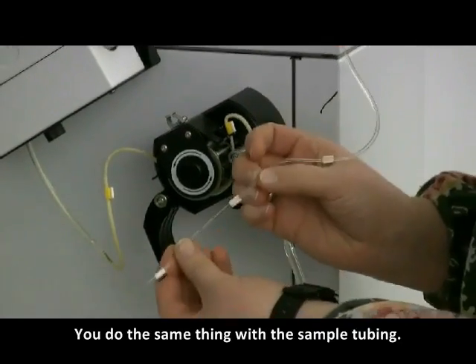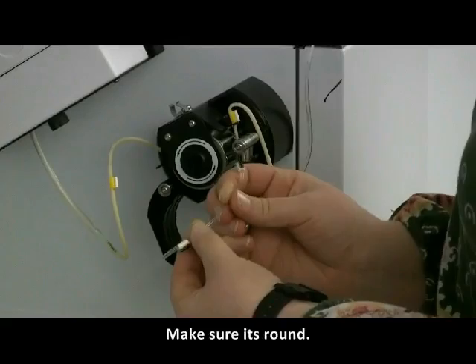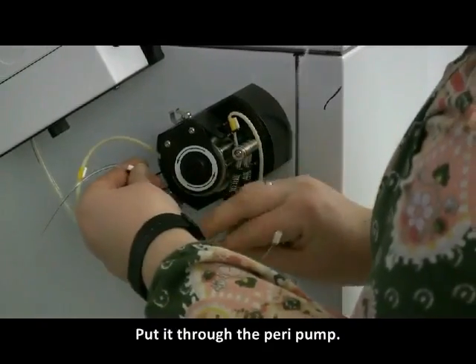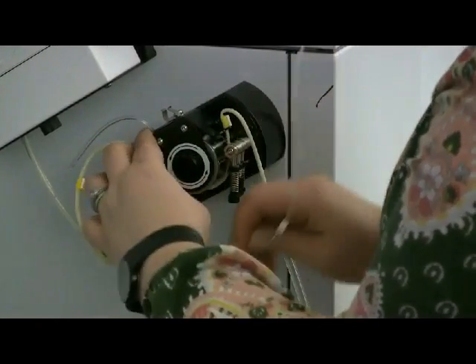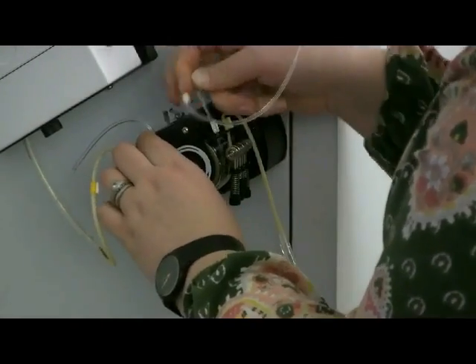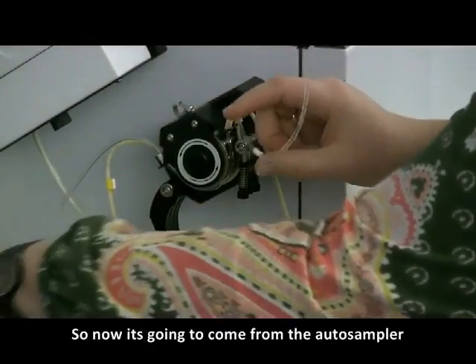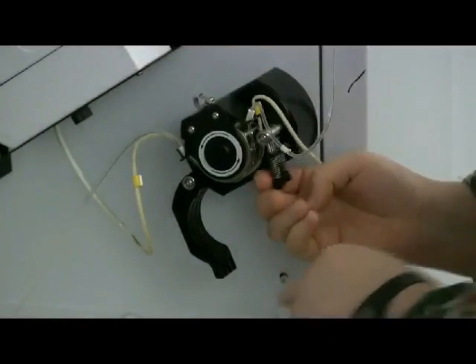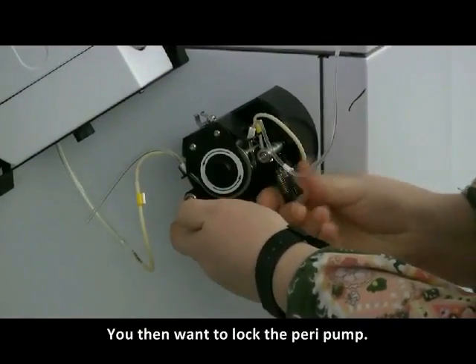Do the same thing with the sample tubing. Make sure it's round. Put it through the peri pump. Now it's going to come from the autosampler, around the peri pump, and into the instrument. Then you want to lock the peri pump.